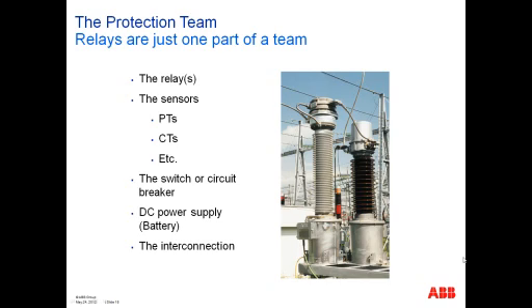Relays operate not alone, but as part of a team. The relays that are most often used require being able to read the system quantities: voltage, current, frequency, etc. And to do this, you need the appropriate sensors like a potential transformer, coupling capacitor voltage transformer or some type of transformation from primary system voltage to a secondary voltage, which would be safe for the relay. The same for the CTs, being able to read the current that exists up at the higher potentials and being able to read them at the secondary.